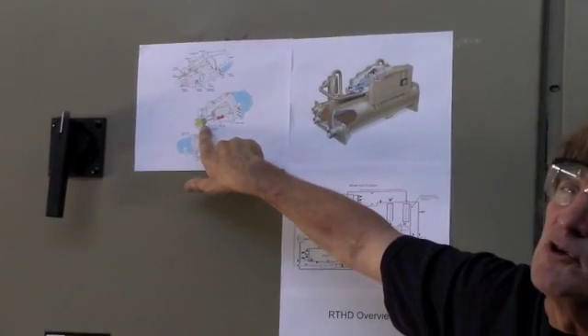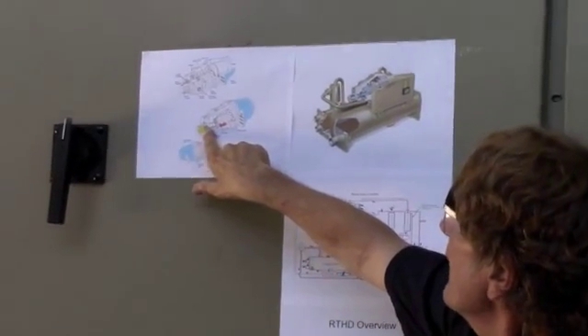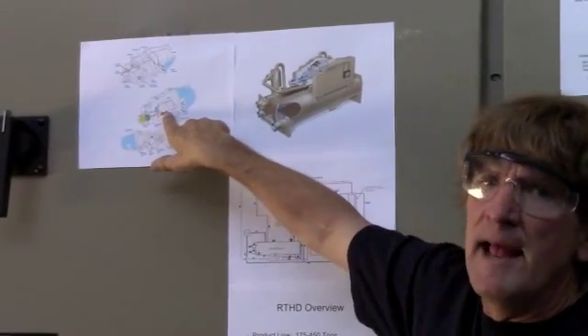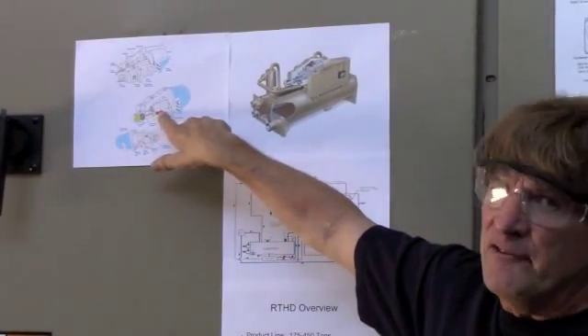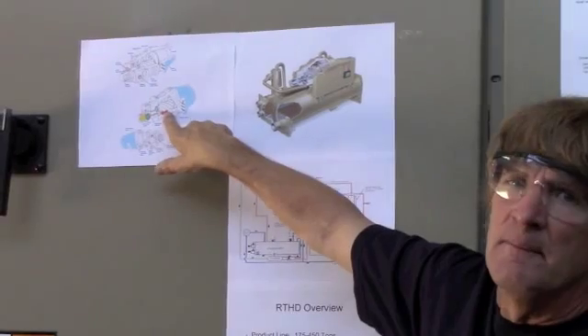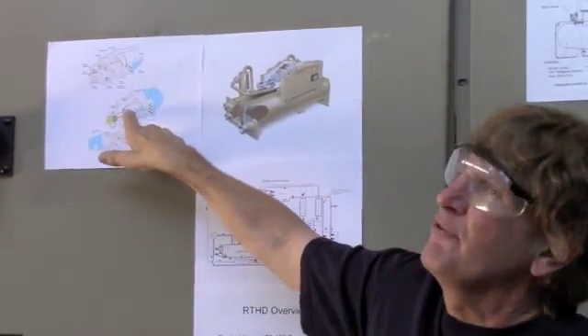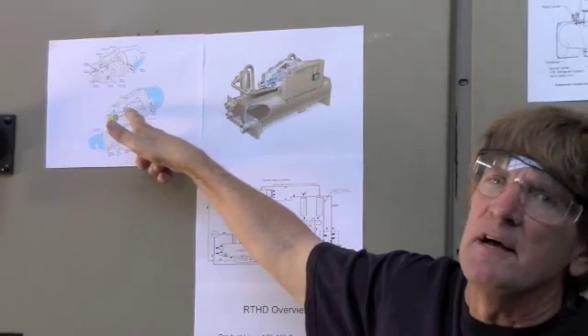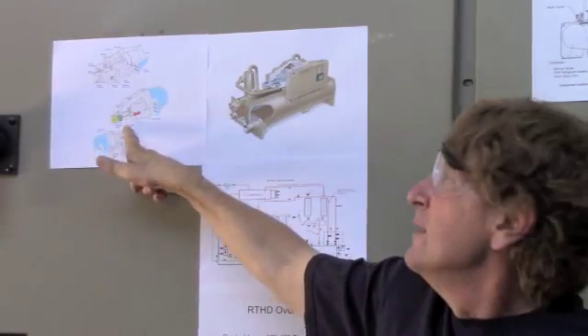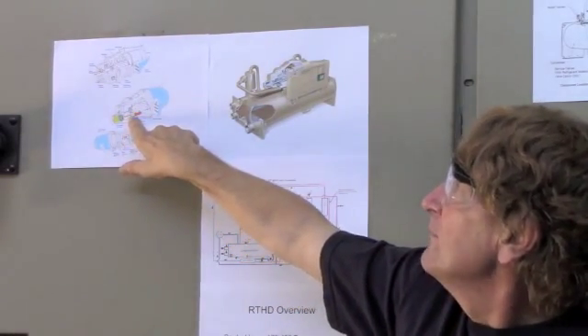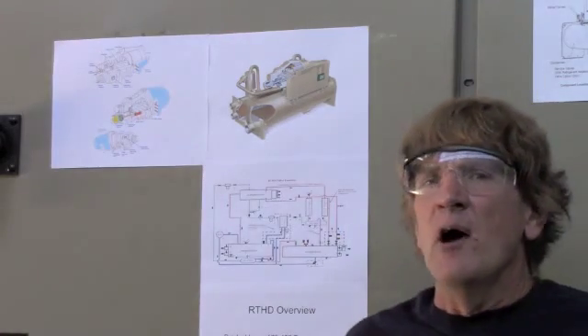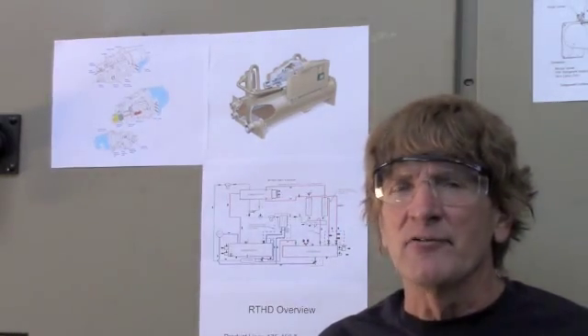Which is used for loading and unloading this compressor. This slide valve will push forward and increase the capacity of this compressor, or go back and reduce the capacity of this compressor. So, this is called a slide valve. Now, what we'll do is we'll take a look at the back side of this compressor.